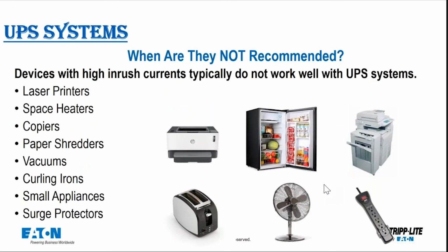Okay, a quick review on UPS systems. These are computer grade UPS systems from Tripp Lite, so they're really not meant for any kind of compressor inrush. We can cover products from a surge aspect or line conditioning, but with this UPS system topology, devices with high inrush are no-nos, for lack of a better term. These UPSs can generally wear down sooner rather than later if put on that kind of load.